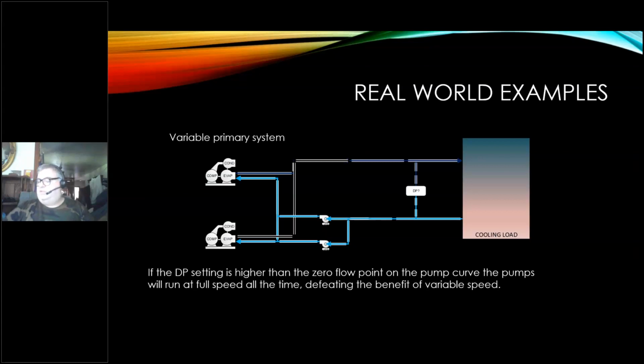So what we typically end up doing is we change the pump speed based on a system change out there and reset that pressure differential setting to change as the system changes. Probably the simplest would be to look at a chilled water valve, in this case chilled water, to maintain it wide open. If it starts closing, I slow down the pumps, and then it'll open back up, and then I'll speed them back up. But I'll constantly be changing the pump speeds in response to what's going on out there in the system, rather than actually measuring and changing my differential pressure, hoping that I'm doing the right job.